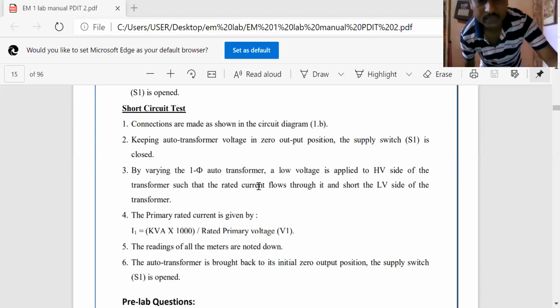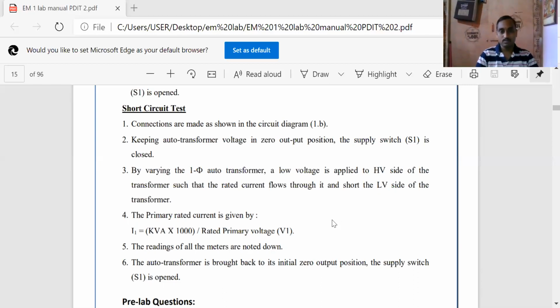With 2 kVA rating, where kVA means K is 1000, and the rated primary voltage of 230 volt, you calculate that. You will get 8.66 ampere for 2 kVA, and 4.3 ampere for 1 kVA. If you use the 1 kVA transformer, it is 4.3 ampere. If you are using the 2 kVA transformer, your full load current I1 is equal to 8.6 ampere. In this case, you have short circuited the secondary terminal. Hence, don't apply 230 volt here.